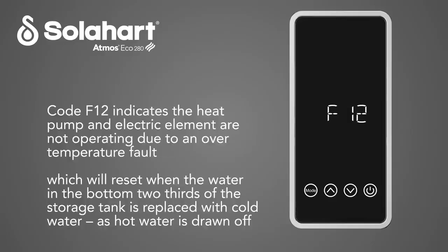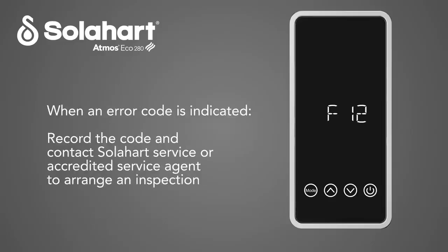Code F12 indicates the heat pump and electric element are not operating due to an over-temperature fault, which will reset when the water in the bottom 2/3 of the storage tank is replaced with cold water as hot water is drawn off. When an error code is indicated, record the code and contact the Solahart service team or your nearest accredited service agent to arrange an inspection.